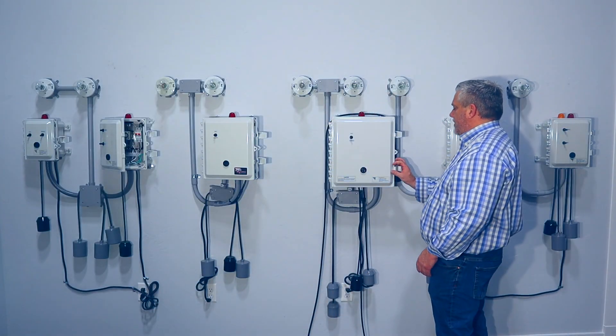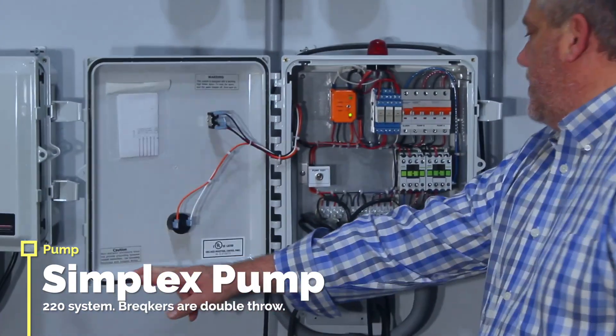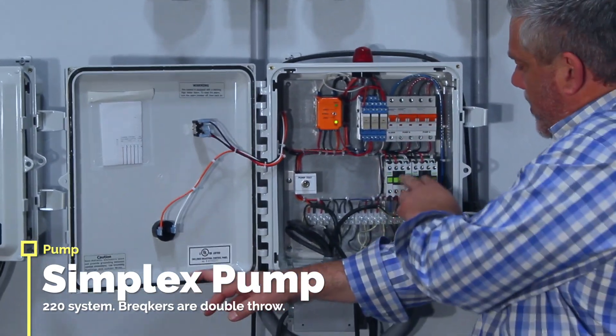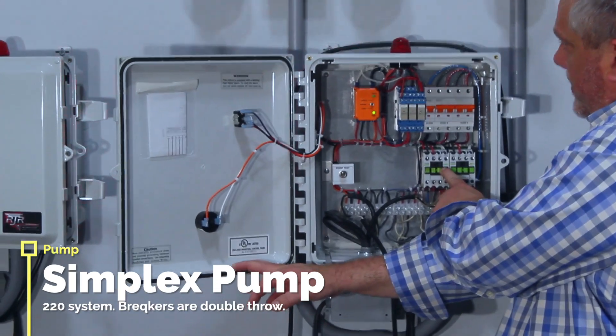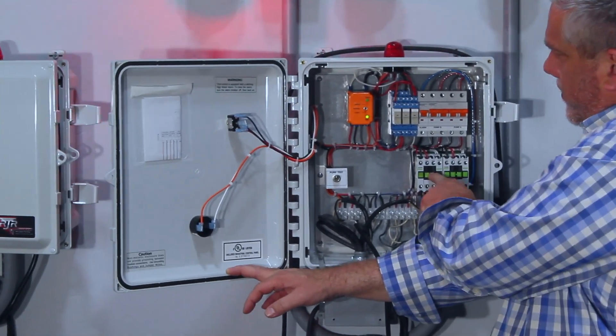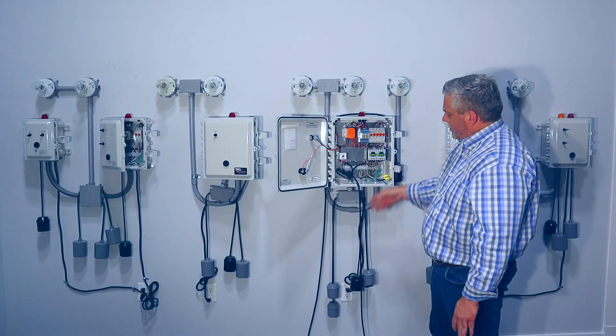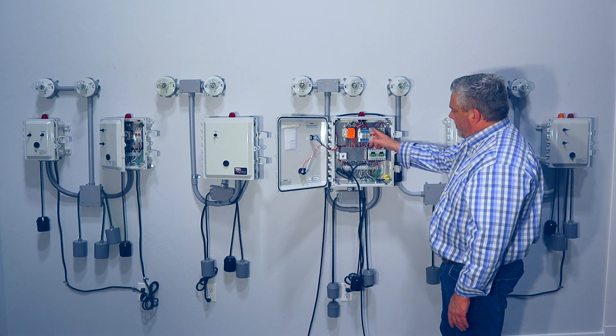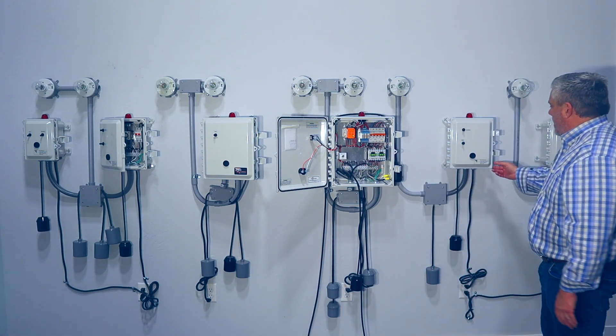Then you have a simplex panel for 220 volts, and you'll see the difference — it has much bigger breakers that are double-throw and big contactors. There's that pump and then there's that pump; when these close, that turns on the pump. The contactor actually takes the load rather than the float, so the relay kicks off and sends it out, turning the pump on.